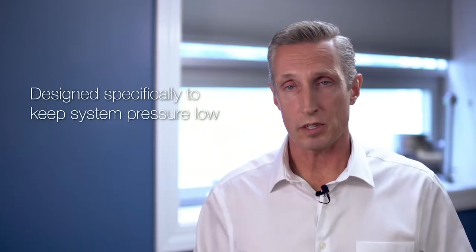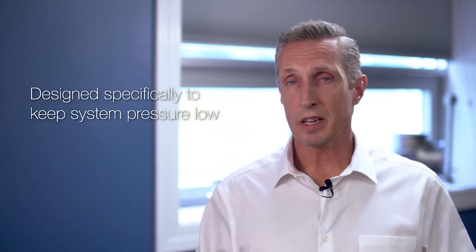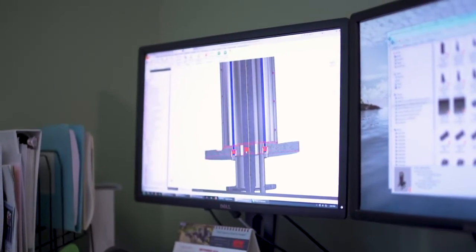Many times these static systems can result in very high pressures if the products are becoming very thick. And that's where the scraped surface heat exchanger comes in as well. The hydraulic diameter can be much larger. We can design it in such a way to minimize pressure drop, and that can have an impact overall on the production of the system, the performance of the system, and the performance of all the equipment in the system.